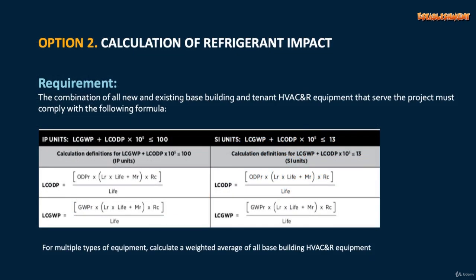For option 2, select refrigerants that are used in HVAC equipment to minimize or eliminate the emission of compounds that contribute to ozone depletion and climate change. The combination of all new and existing base building and tenant HVAC equipment that serve the project must comply with the following formula. The formula looks complicated, but actually is pretty straightforward.